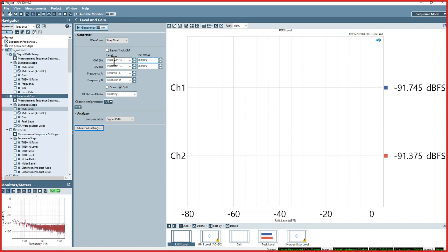All right. Next question. Is there a specific reason in the graphs that you use the stepped sine instead of a much faster chirp? Yeah, I think that's the question I answered previously, which is depending on what frequencies you want to be able to sweep to and what measurement results you want to get, you sometimes just can't use a chirp.